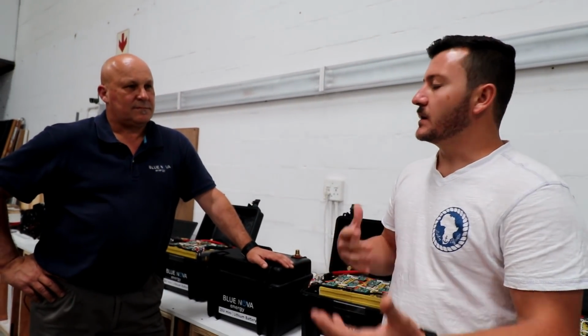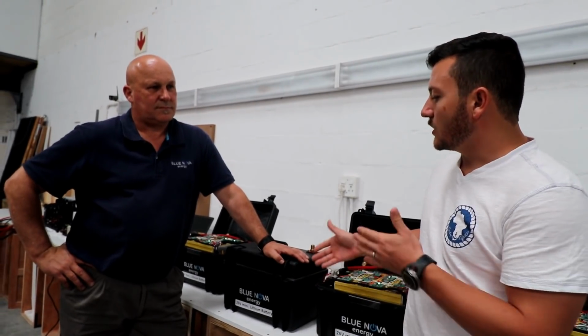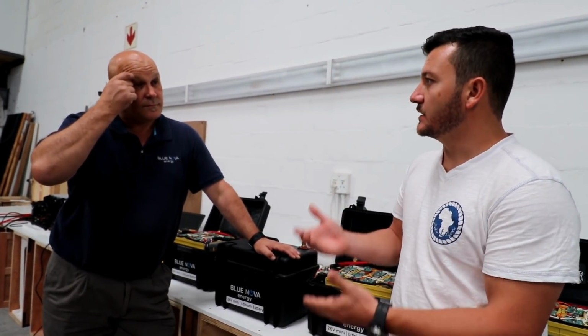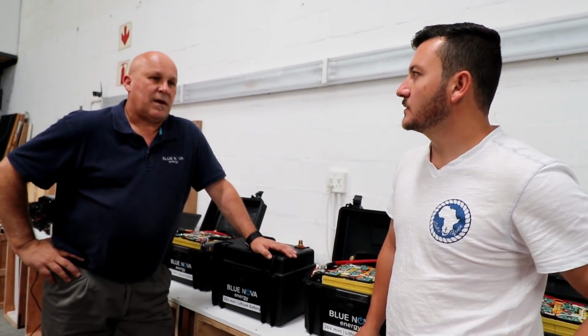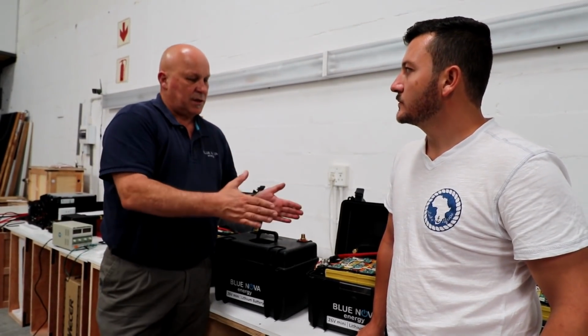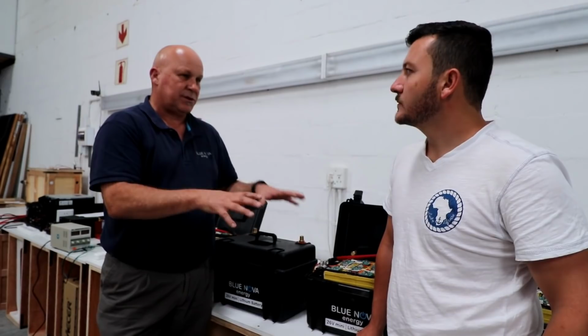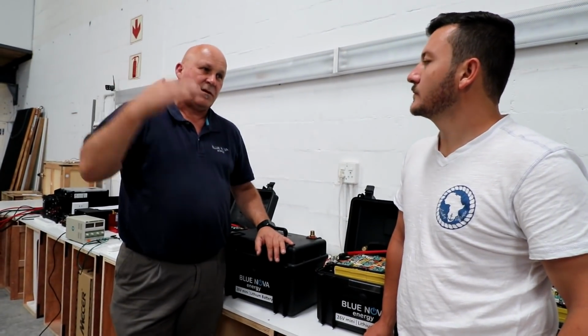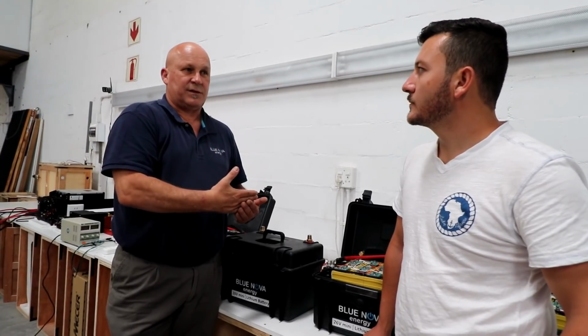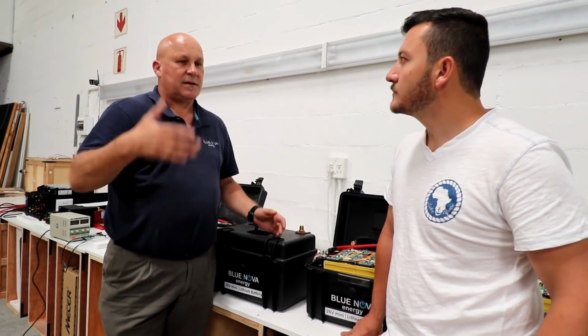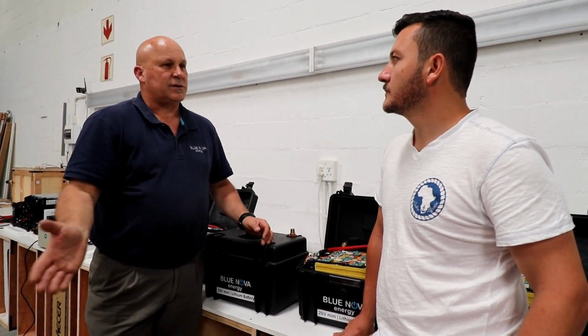What if the system is really demanding, or someone could only afford one battery - could they do multiple charges and discharges in a day, and can the battery handle that? Absolutely. In diesel hybrid scenarios, the generator starts in the morning during peak load - doing dishes, washing, ironing - servicing the electric loads but charging the battery full. By 9 or 11 o'clock they shut down the generator and run the whole day on the battery. At 4 o'clock, during the working period from 4 to 6, they start the generator again, charge the battery full by 6 or 7 that evening, shut it down, and then discharge. If they do a full discharge each time, that counts as 2 cycles, so you'll get about 7 years out of the battery.